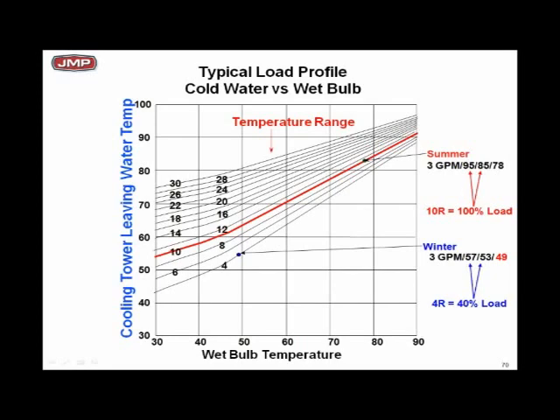Slide that down to 50 degree wet bulb. Nice point to look at on the chart. And tell me, look at the chart, what water temperature can you make? How cold a water can I make with the same cooling tower, with the same load at 50 degree wet bulb? Well, let's take a look. Wow, it looks to me like I'm making, what, about 63 degree water? So I got 50 degree wet bulb. Now I'm making 60 degree water, 63 degree water. I've got an approach of 13 degrees. I got the same load, the same tower. I can only make 63 degree water with 50 degree wet bulb at the same tonnage on my tower.